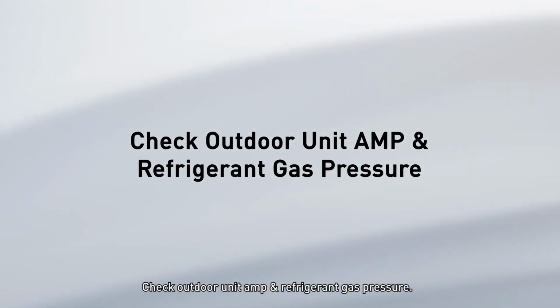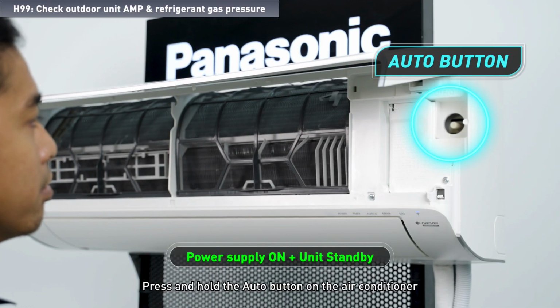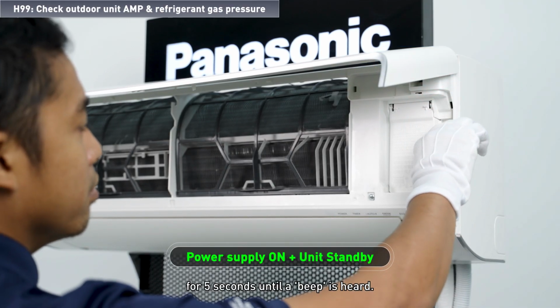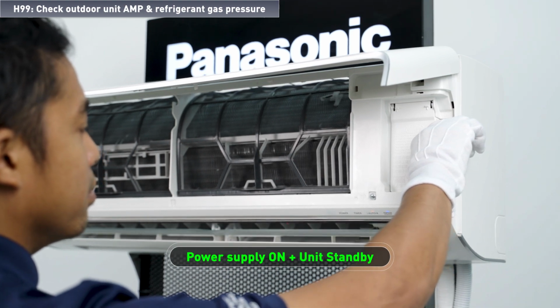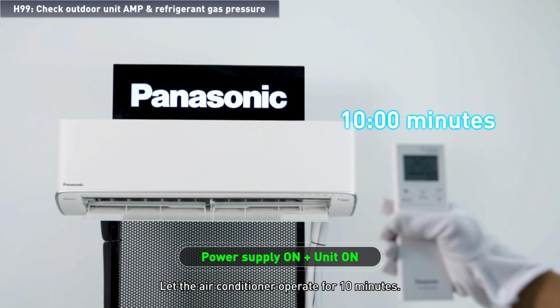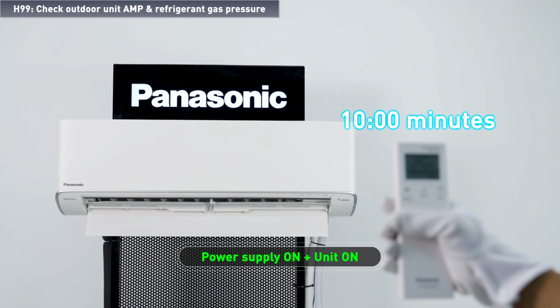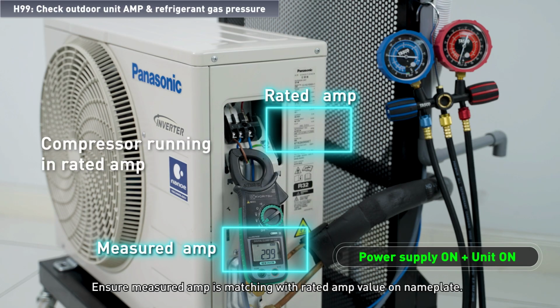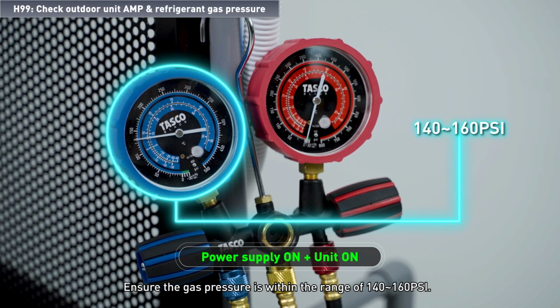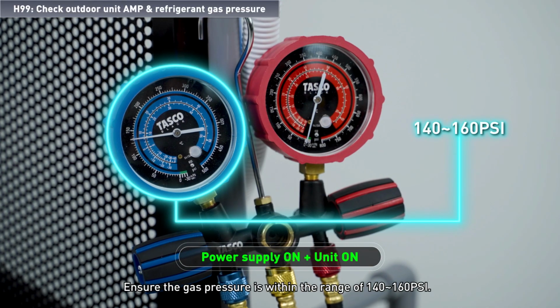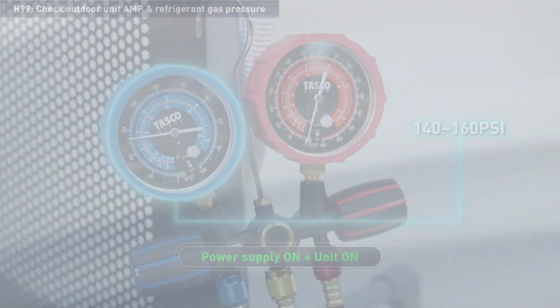Check outdoor unit amp and refrigerant gas pressure. Press and hold the auto button on the air conditioner for 5 seconds until a beep is heard. Let the air conditioner operate for 10 minutes. Ensure measured amp is matching with rated amp value on nameplate. Ensure the gas pressure is within the range of 140 to 160 psi.